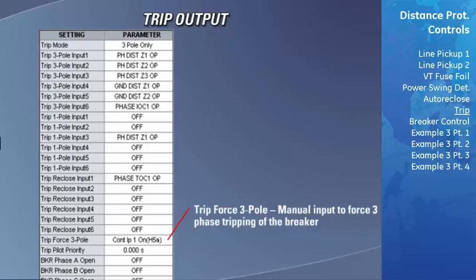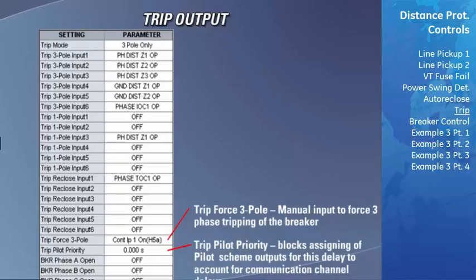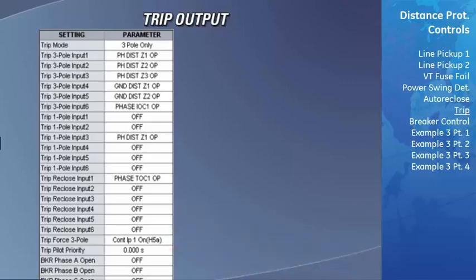The Trip Pilot Priority setting is used to block the assigning of the pilot scheme output operands for a short period to make sure the communication delay will not cause any maloperations. This setting should be set to the inter-relay communication channel delay time plus some additional margin.